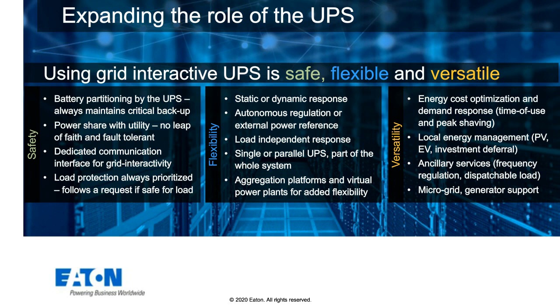You may have thought, why don't we just do this with our generators? And you can, and many clients do. But a generator takes a while to start up and stabilize, and sometimes there are limits on how long you can operate it in many municipalities, whereas a UPS system with battery is instantly available and doesn't have those restrictions. The alternative is that you typically can't run for as long as a generator, assuming you're allowed to.